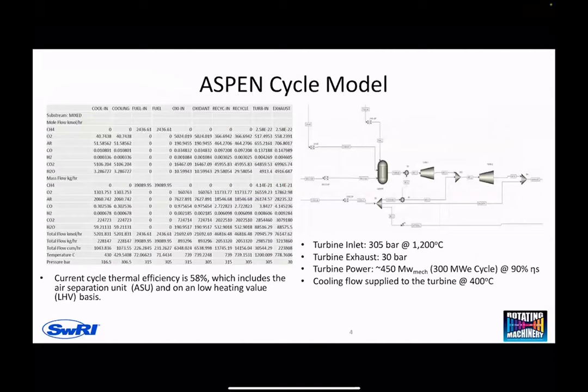So this overlays one of the cycle models, really just focused on the turbine, the cooling flow coming in, the fuel flow, the oxygen, the recycle flow which is mostly CO2. The main design parameters, as I mentioned before, turbine inlet is around 305 bar at 1200 C. Turbine exhaust is 30 bar, so a 10 to 1 pressure ratio. Turbine power is around 450 megawatt mechanical for a 300 megawatt cycle.